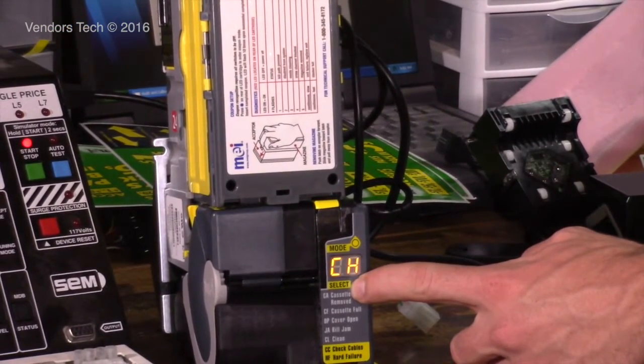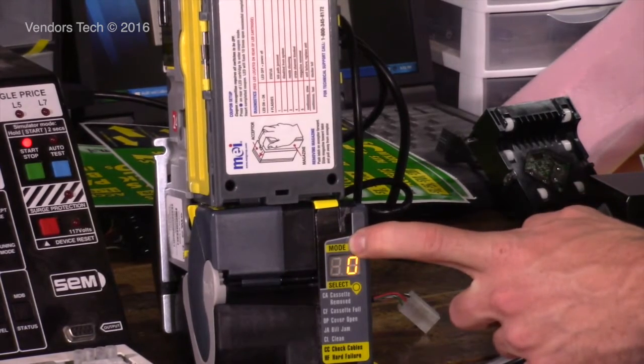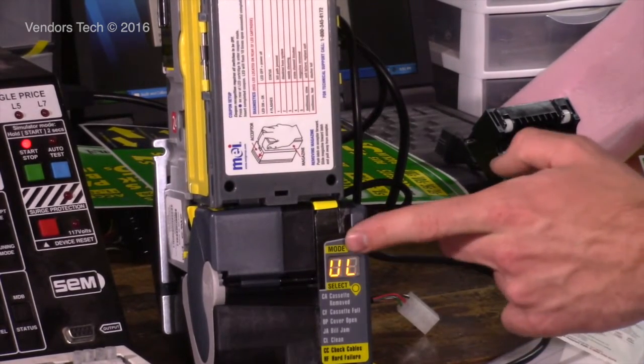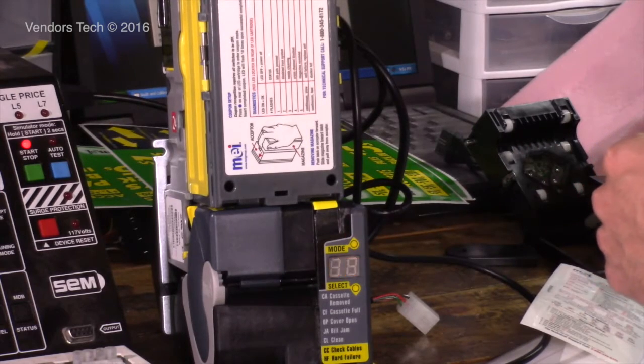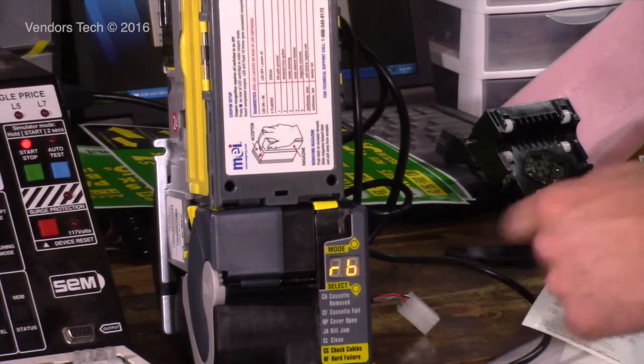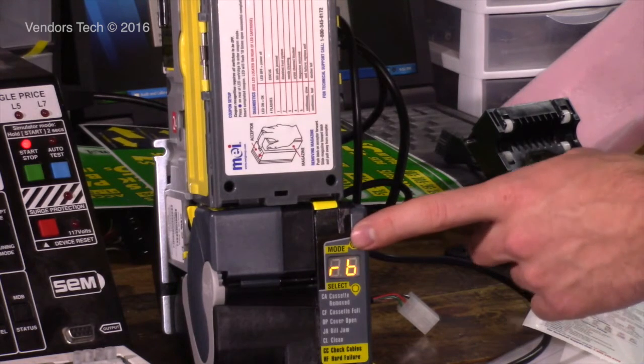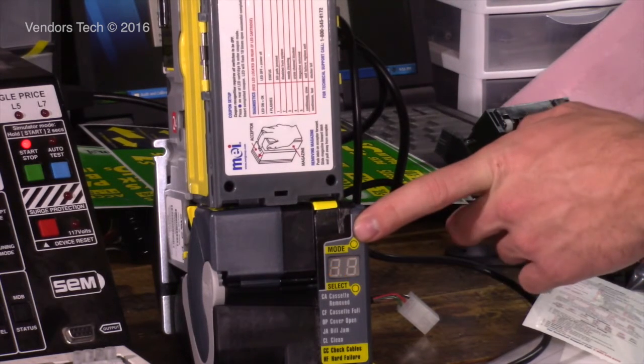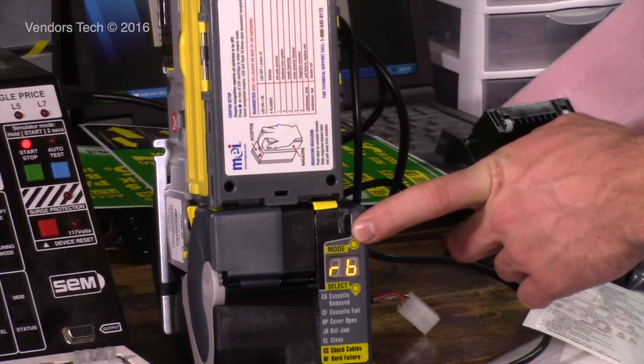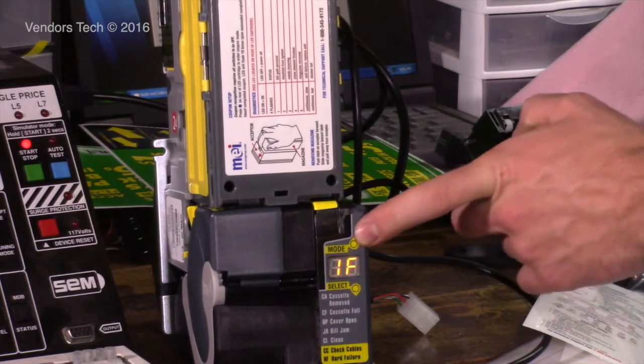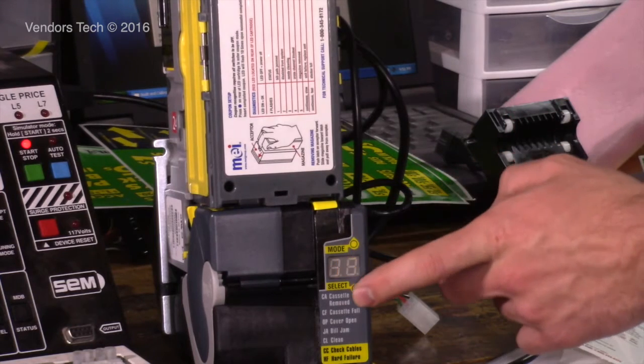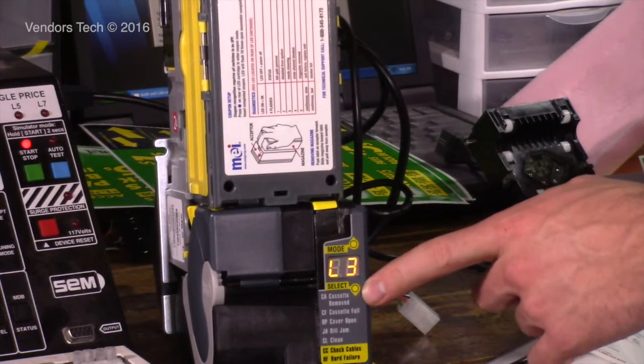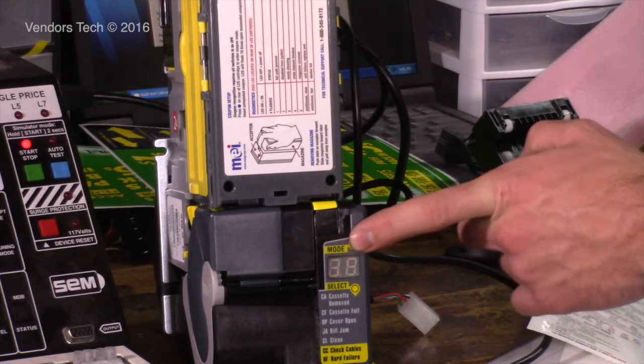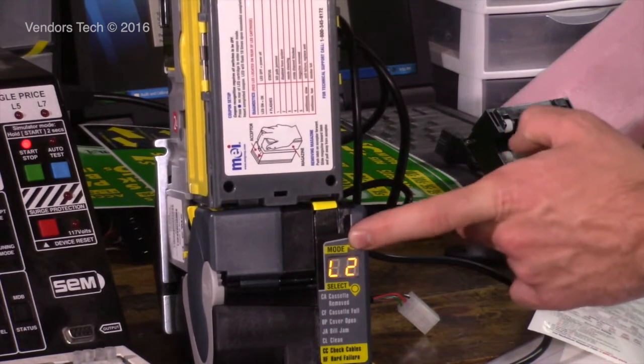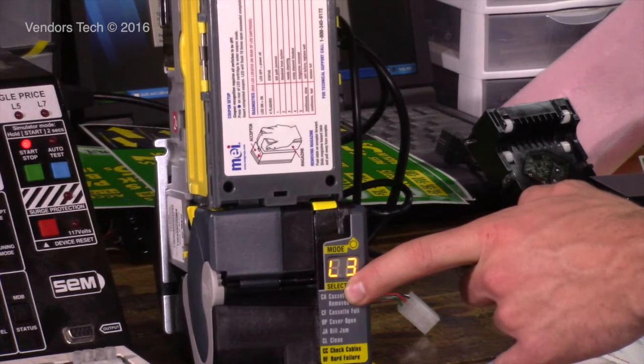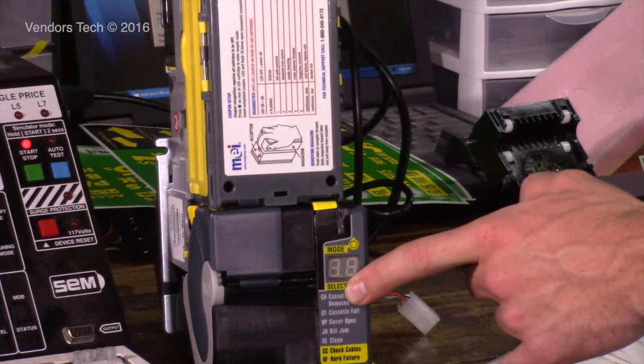So here we go. It timed out, so I'm going to jump in again. It says LD, I'm going to hit the mode button until it says SU. Then I'm going to hit the select button to enter SU, which is your setup mode. Hit the mode button, it says RB once you get into setup. I'm going to hit my mode button here. Interface, I'm just going to double check. You want it to say L3, which this is new, so... Level 3 MDB. I'm just going to make sure all these are where they should be.